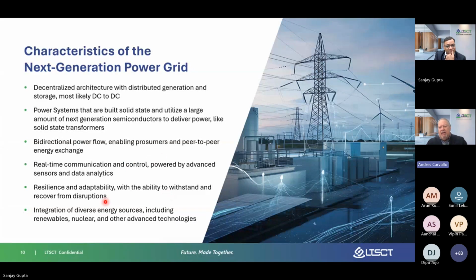The importance of this shift is that you're moving away from inertia-based synchronization, which gives you anywhere from 5 to 10 seconds to make a decision. That seems like not a lot, but in grid time, 5 to 10 seconds is an eternity, and that's how the grid is managed today, with a few people at a time managing every grid power station. Now there needs to be inverter-based synchronization, within a cycle or two cycle times, which is 1 divided by 50 or 1 divided by 60, so anywhere from 17 to 20 milliseconds depending on geography. Suddenly 10 seconds looks like an eternity compared to 20 milliseconds.